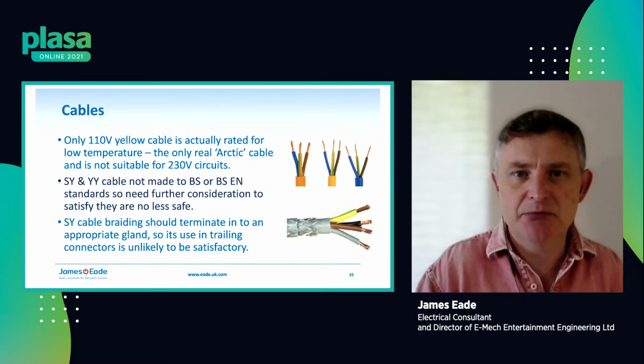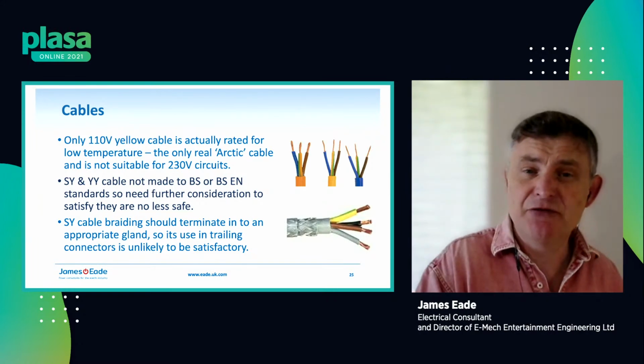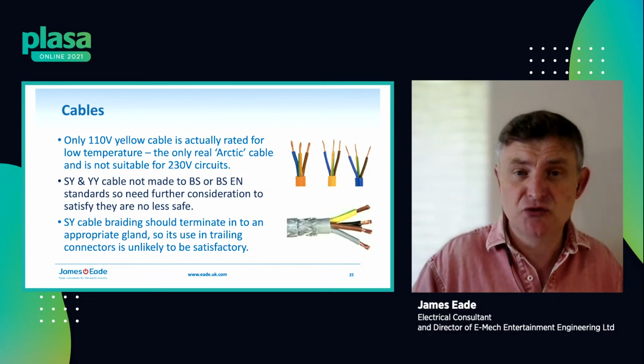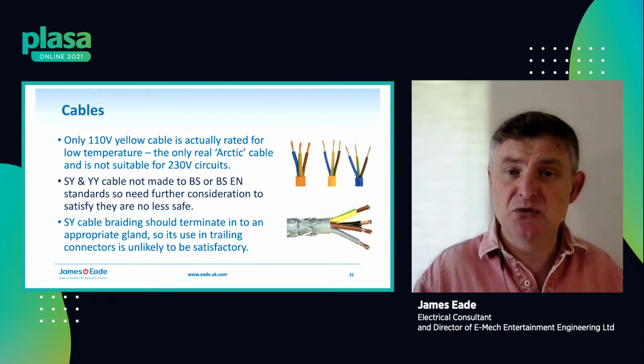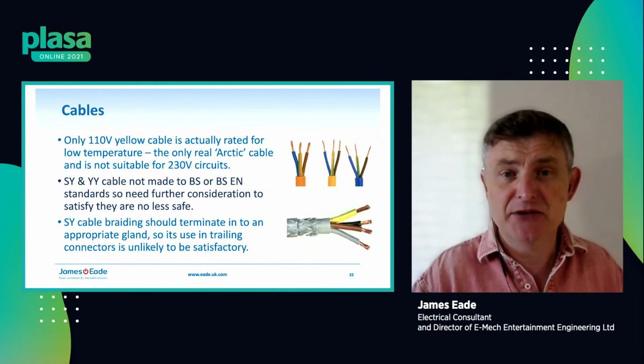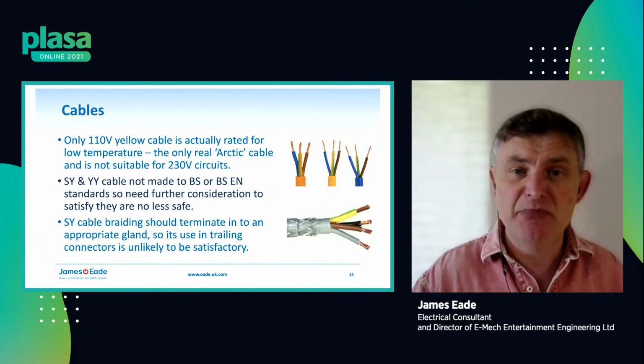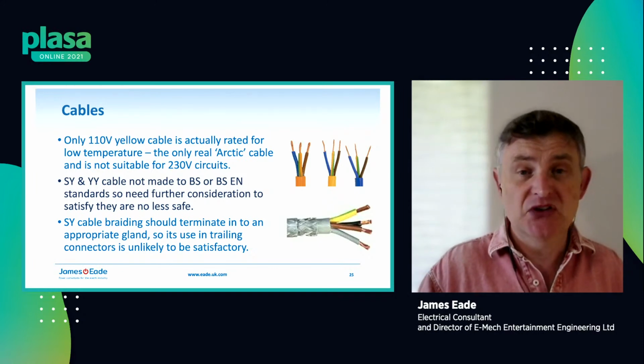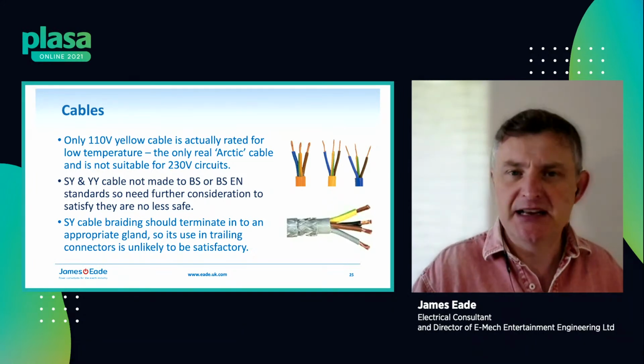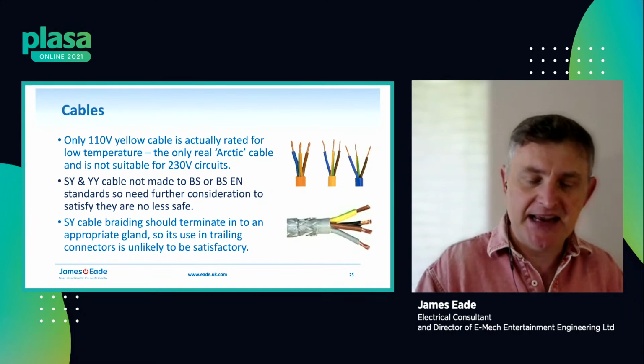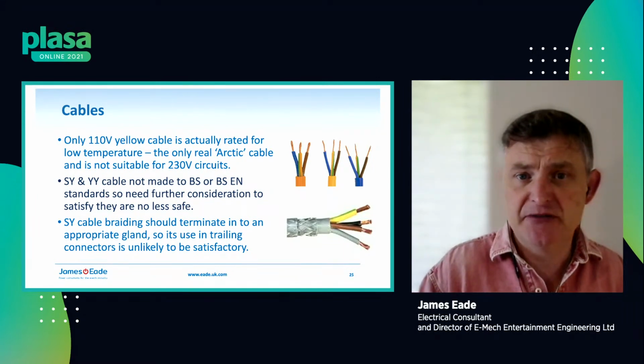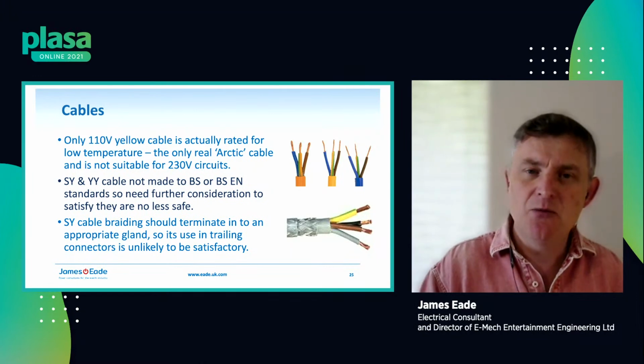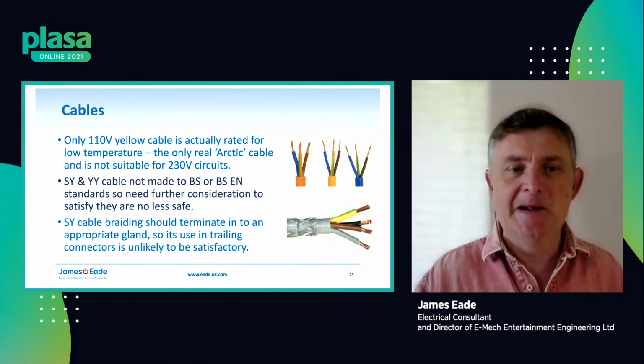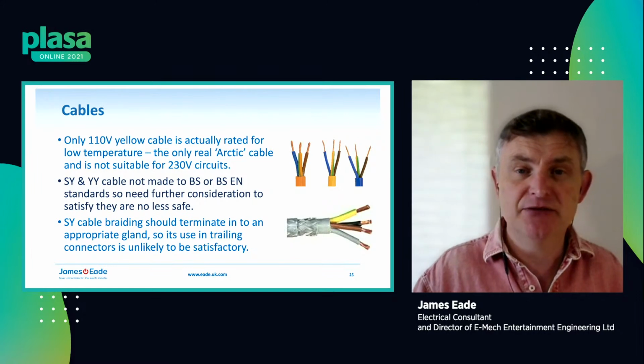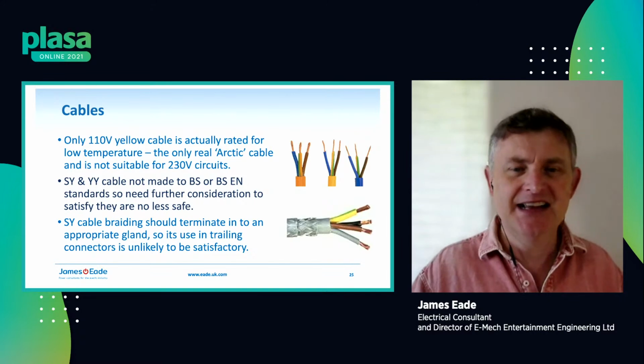It's a screen for the cables going back up, and it's designed for indoor use. When you read the manufacturer's instructions, it'll say if using outdoors, particularly in temperatures less than 5 degrees, fix it permanently so it can't be bent. And I've seen countless examples of loading bays and similar where this type of cable is used. The outer clear plastic has suffered UV degradation. It's all cracked up, water's got in, the braiding is rusted, and the insulation is all getting damaged and deformed. So it's very important to make sure that it's used only in appropriate instances.